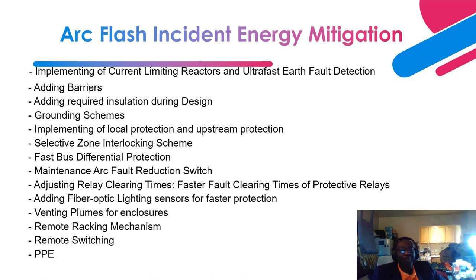This is the last slide — mitigation techniques. If you run your simulation and determine you are not meeting the requirements, NFPA 70E indicates you need to implement mitigation techniques. The first option during the design stage is implementing current-limiting reactors — air-core type that does not allow saturation, unlike iron-core types. Next is ultra-fast arc flash detection devices, which detect incident energy very quickly and divert it to ground.